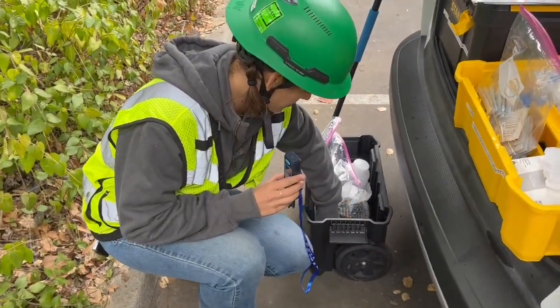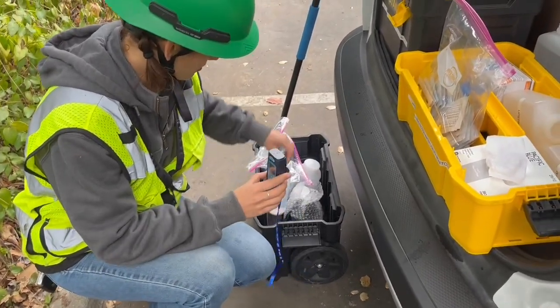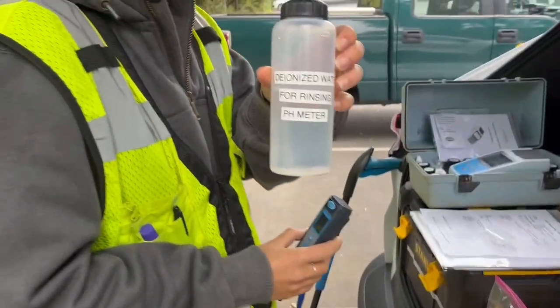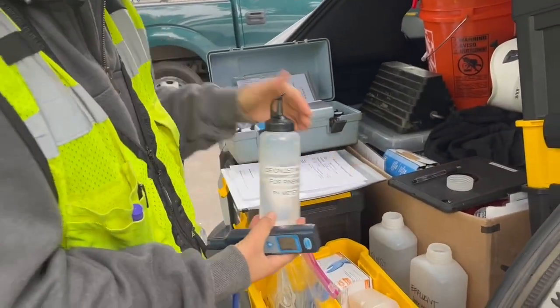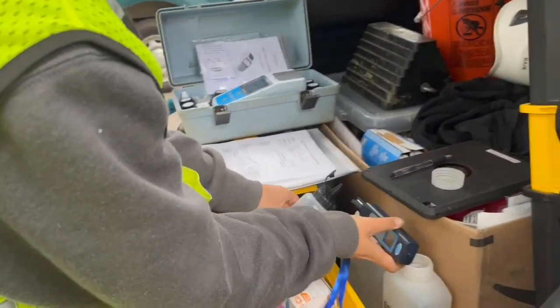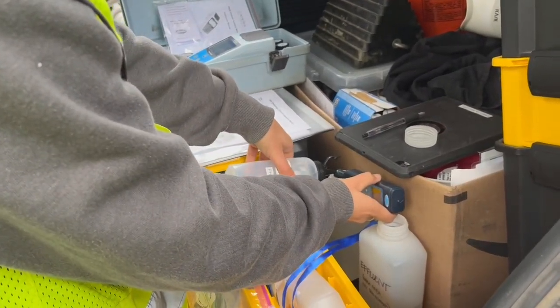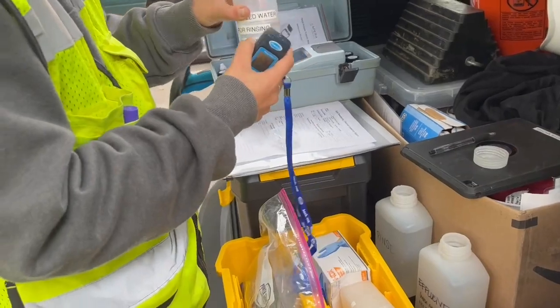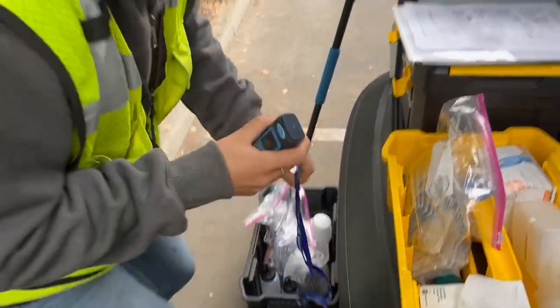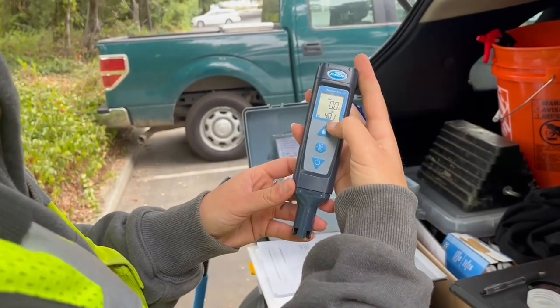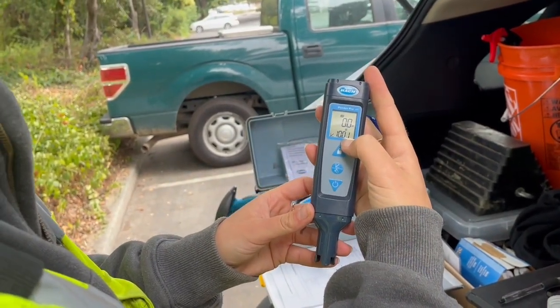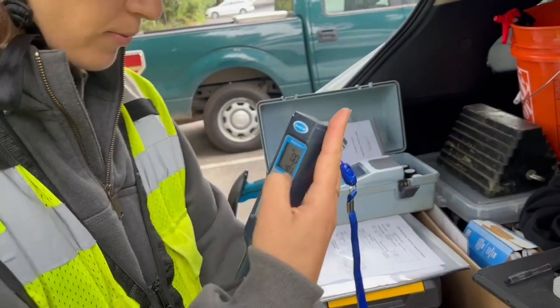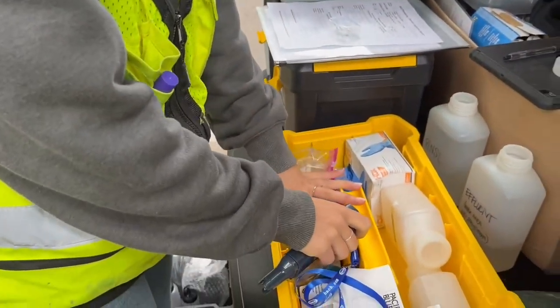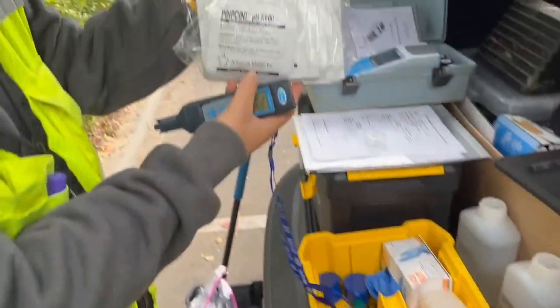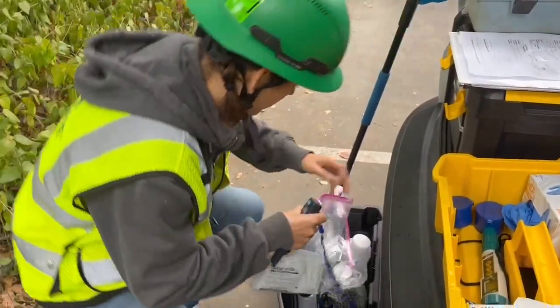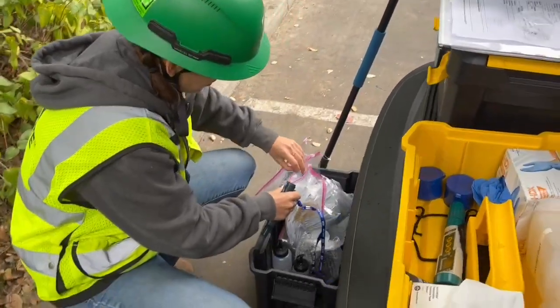The next thing I'm going to do is rinse it with deionized water. Got a rinse bottle right here. So I'll just carefully hold the probe over the opening of the bottle and rinse it. Voila. Recap the rinse bottle, set it aside, and next the meter will flash either 4 or 10. We can do a 2-step calibration with either the 4 or the 10 solution.